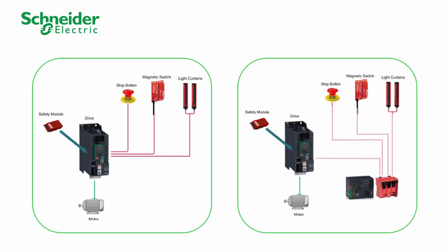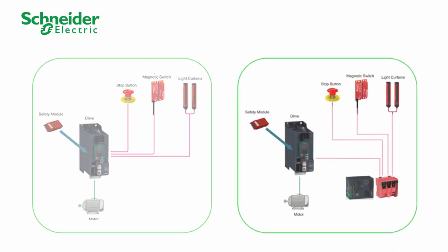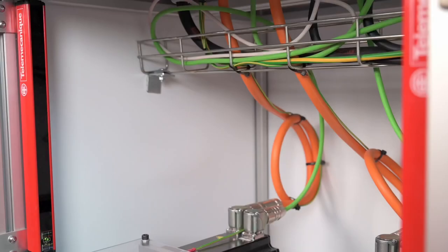There are two ways we can activate safety functions. The first is by connecting safety sensors directly to the safety module. The second possibility is by connecting safety sensors and also the safety module to a safety PLC — the M262 and TM5SLS safety.